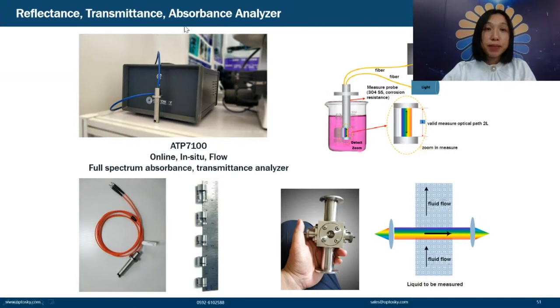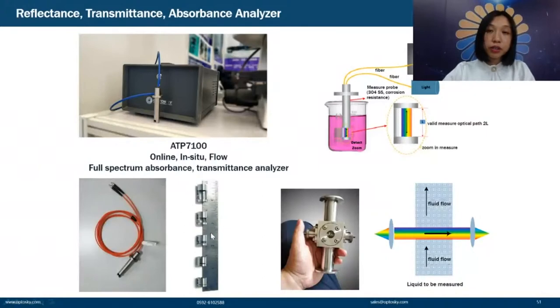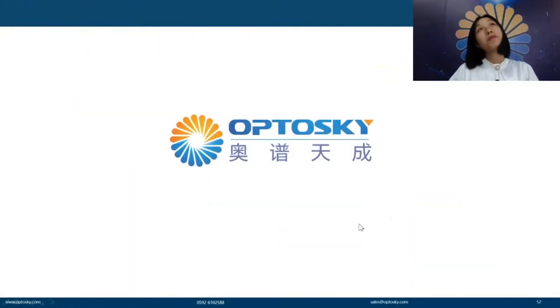Finally, the ATP-7100 is a reflectance, transmittance, and absorbance analyzer that enables online, in-situ, and flow-through monitoring. The detector zone has a measurement optical path, a probe is inserted into the sample, and the light source connects via fiber. The spectrometer analyzes the resulting spectrum. The probe configuration can be changed to realize online measurement in different process environments. That concludes the presentation — thank you.